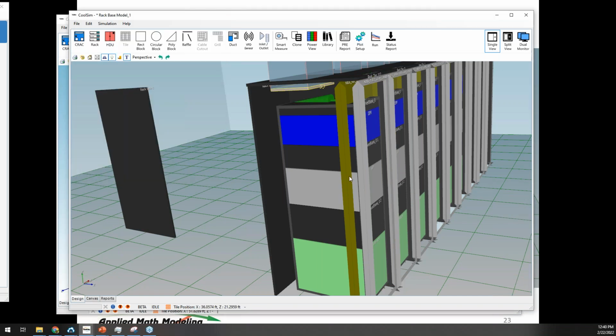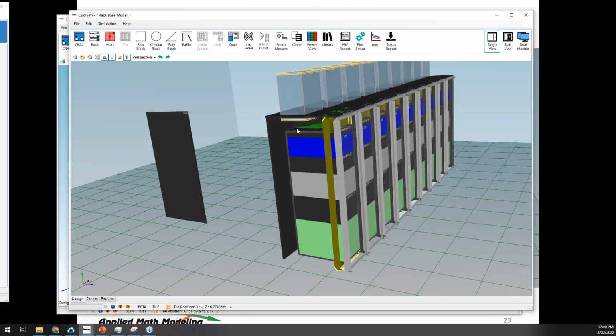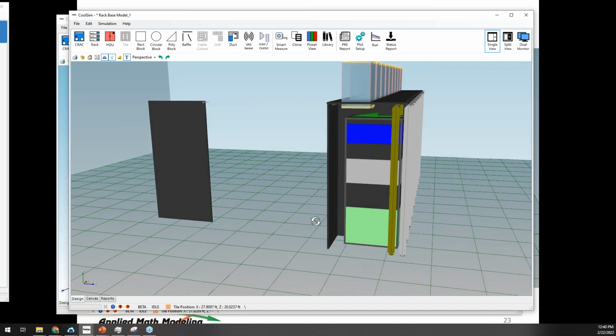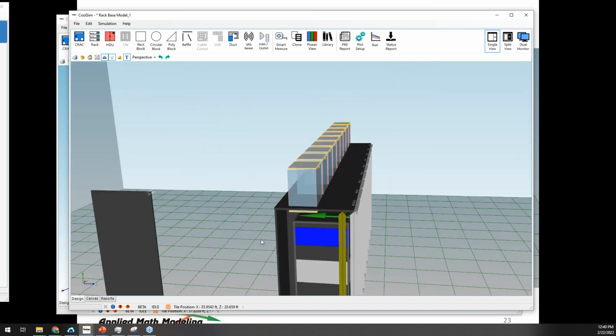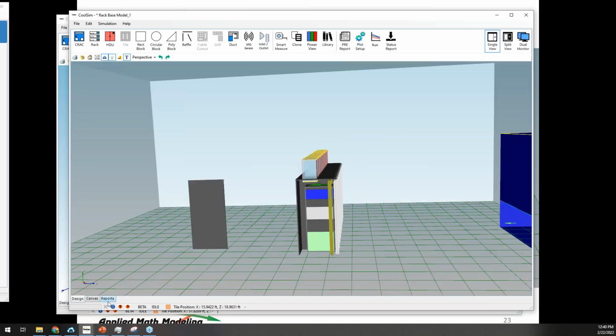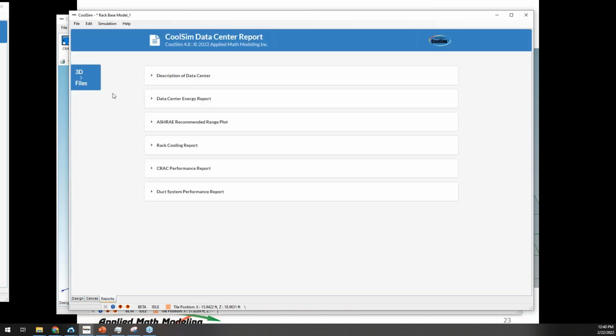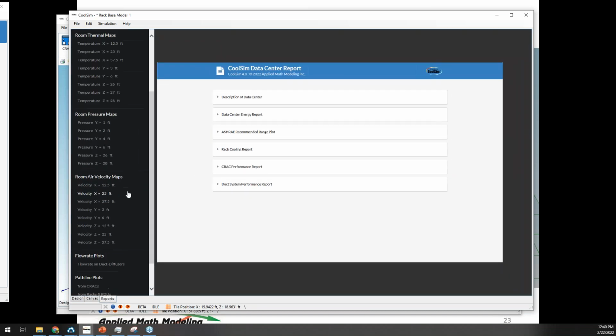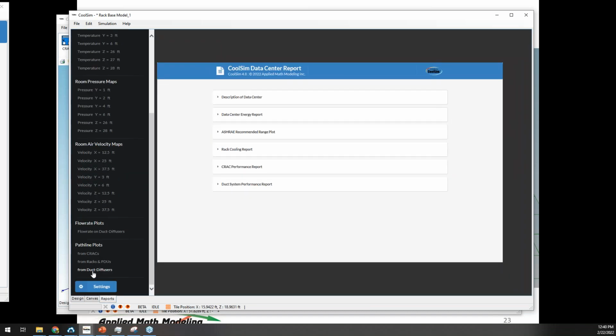And you can set all these rack rails to leak. You could even take one rack rail and put it across the whole row, because all I did is take the first group and clone it. But the air will come out of the back of this and supposedly just go up through the chimney. But it doesn't always work that way. So here is some output for that particular model. And I want to show you what's happening. So let's go to the racks and PDUs right here.